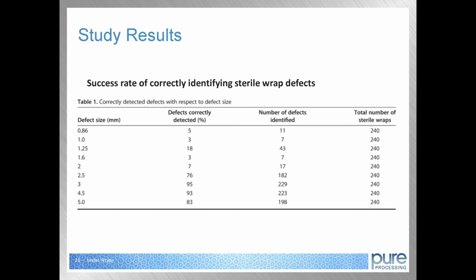Then there's a dramatic increase in detecting defects once we get to 2.5 millimeters, jumping to 76%. Then it goes to 95%, 93%, and 83%. So what this table really shows us is that we're not accurate, and we're not doing a good job inspecting sterile wrapping to determine whether there are holes.